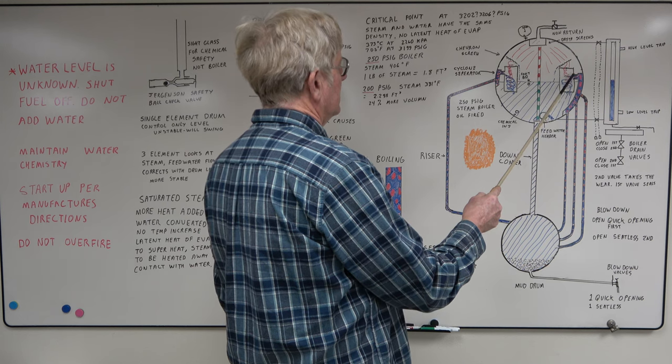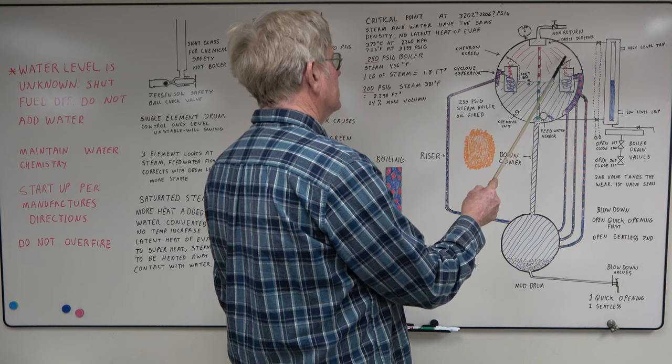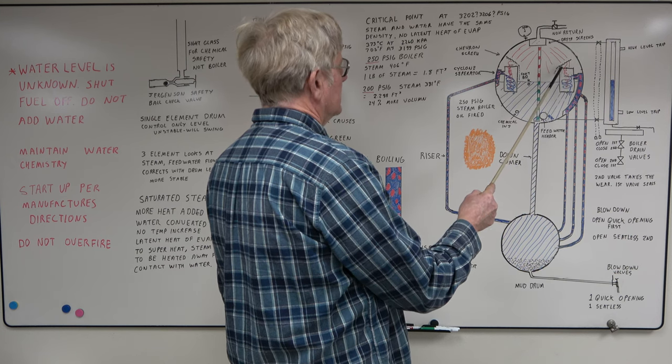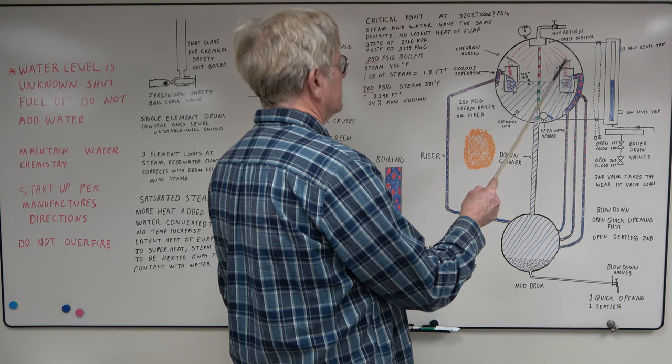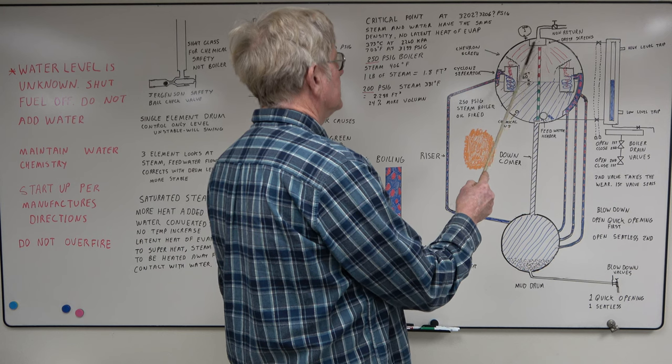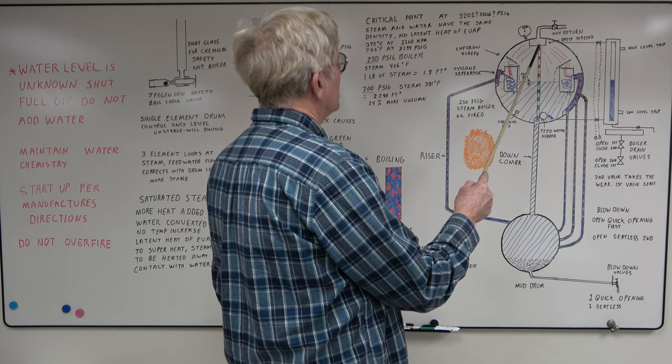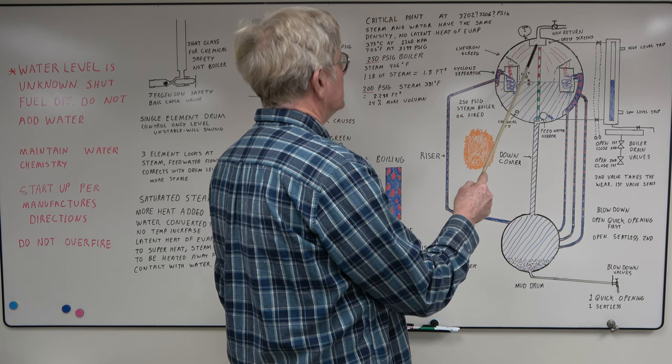The cyclone separator, it spins the mixture. The water's flung to the outside and drains out. Steam comes up the center. It goes through the chevron dryer screens. This creates a tortuous path where the water droplets stick to the plates and then drain off. Up here we have another set of dryer screens. These can go across the boiler. The whole purpose of these is to dry the steam, get rid of any moisture droplets.